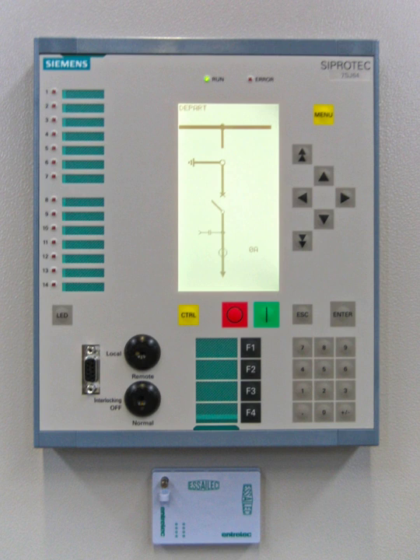Topic: Earth fault, ground fault. Earth fault protection also requires current transformers and senses an imbalance in a three-phase circuit. Normally the three-phase currents are in balance, i.e. roughly equal in magnitude. If one or two phases become connected to Earth via a low impedance path, their magnitudes will increase dramatically, as will current imbalance. If this imbalance exceeds a predetermined value, a circuit breaker should operate. Restricted earth fault protection is a type of earth fault protection which looks for earth fault between two sets of current transformers, hence restricted to that zone.